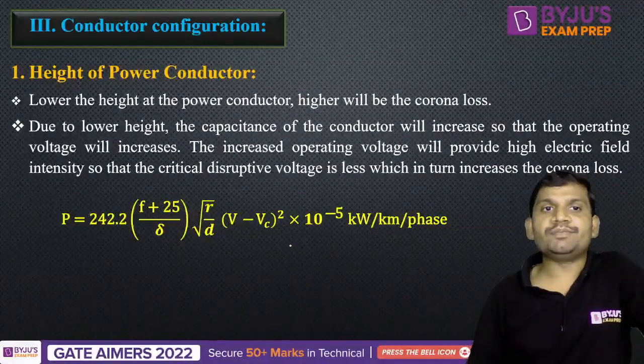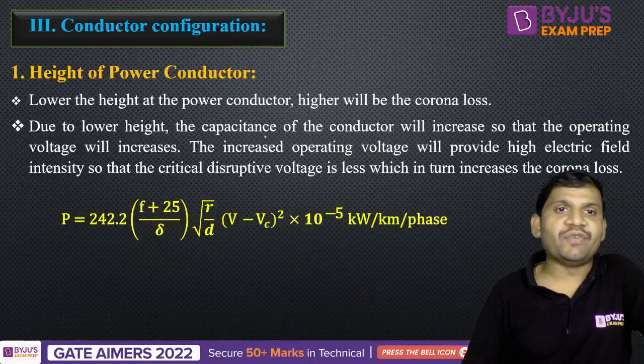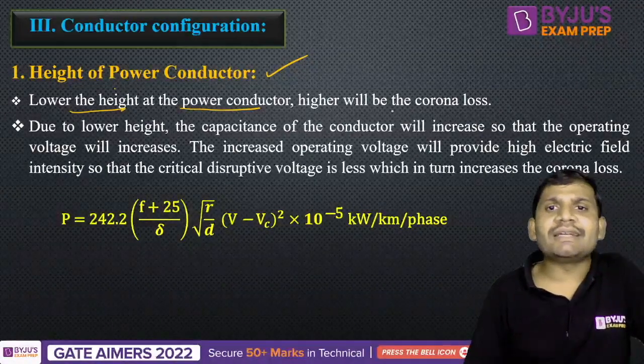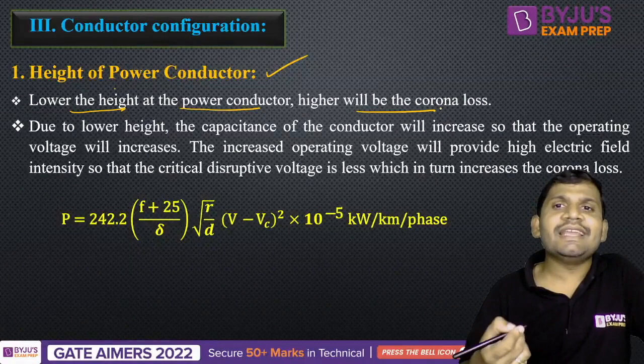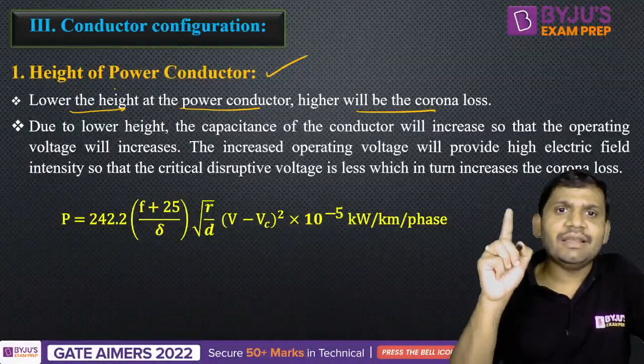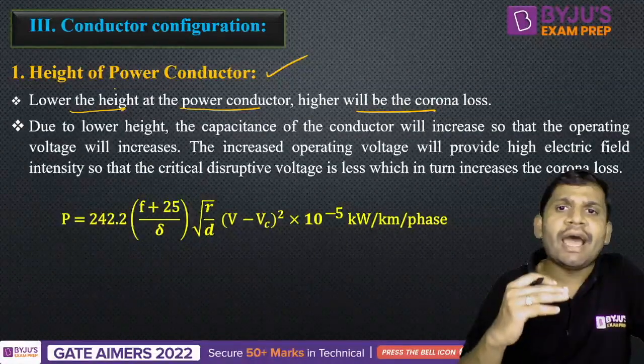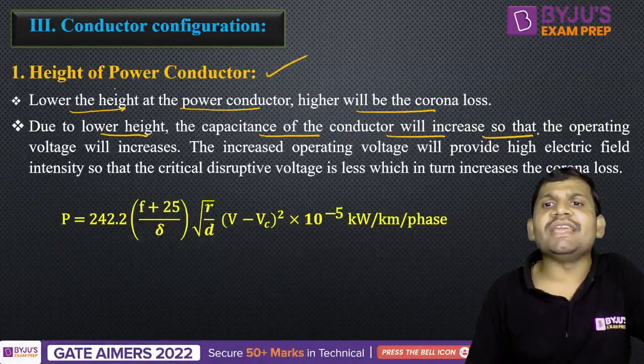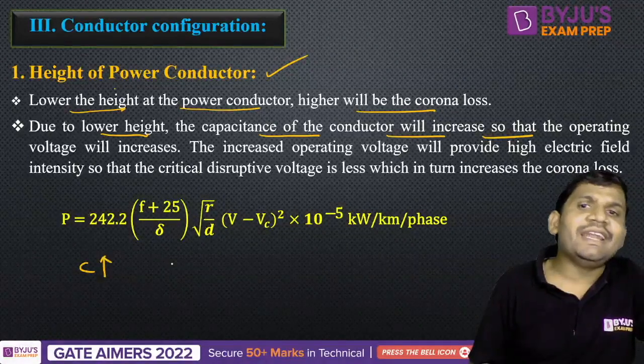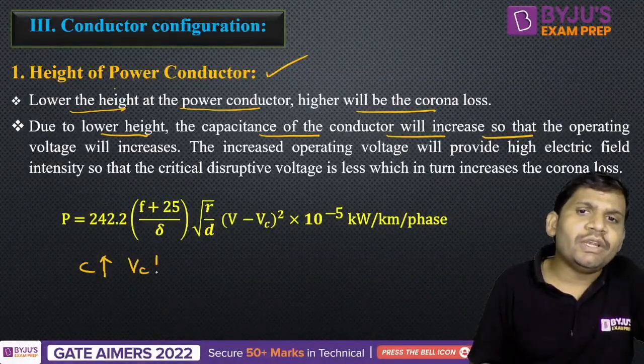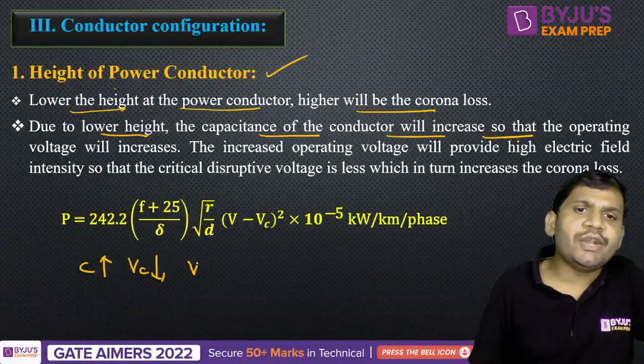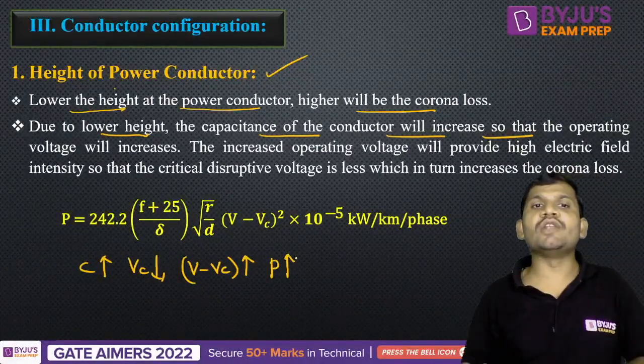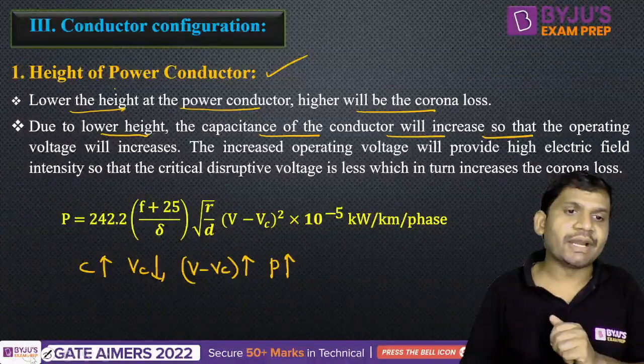Next, conductor configuration. One factor is the height of the power conductor. Lower the height of the power conductor, higher will be the corona loss. That is why we maintain transmission lines at more height. Due to lower height, the capacitance of the conductor increases. Once the capacitance increases, the critical disruptive voltage reduces. Once V minus Vc increases, the power loss also increases.